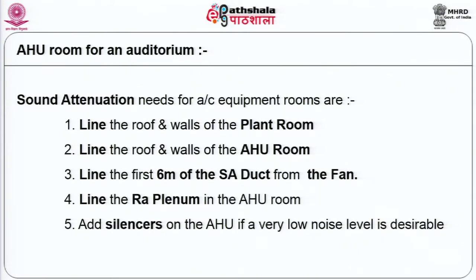walls should be lined. Now, roof lining is one of the most effective devices because regardless of where the source of sound may be, for instance, in a plant room you might have a pump, you might have a compressor, you might have, let us say, a valve which is making noise. Now, if you line the roof, it is a good chance that any of these equipment will be in direct line of communication with the roof. And since noise travels in a straight line, the noise emanated by this equipment at its first reflection will tend to get reduced if you line up the room.